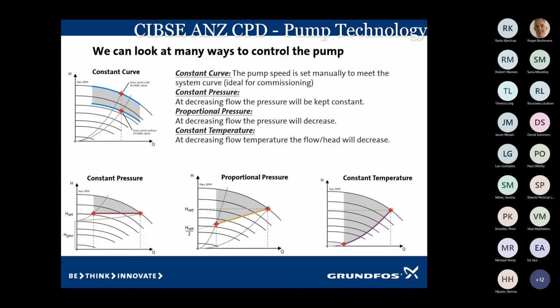And then temperature control, we're able to actually reduce the temperature way down. And this is typical of a domestic hot water loop. You've got a return main or a ring coming back, putting a small pump on the return leg and VSD it and run it on temperature. And you can see that at low loads, when there's no demand, it's running like a light bulb. There's not a lot of energy at all coming from that.